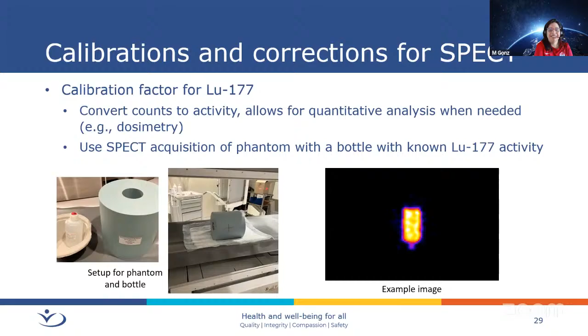That was part of the SPECT working group: we had to determine what clinical parameters we were going to use. Here is the spectrum for lutetium. Therapy papers have been published, and a lot of the physicists at BC Cancer have been doing this, and we decided we were only going to use the 208 keV peak to image it. We're not going to use the 113, because 208 is a cleaner peak. Around the 113, there's a lot of scatter that affects the image quality.